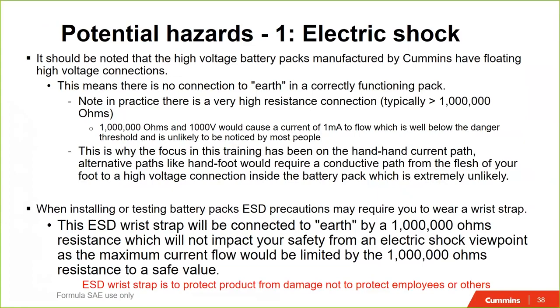There is typically, certainly in automotive packs, a high resistance connection which we use for measuring ground faults as part of the startup before we engage the contactors. This is a high impedance connection, typically over 1 megaohm. If you do the simple maths, even at 1,000 volts, that's a current of less than 1 milliamp, which most people don't even feel.